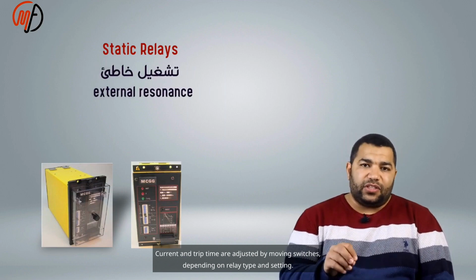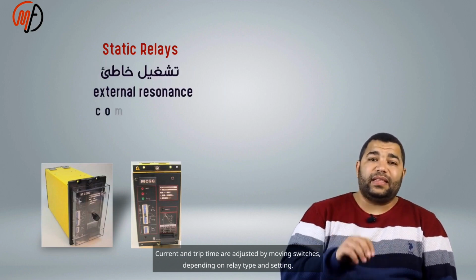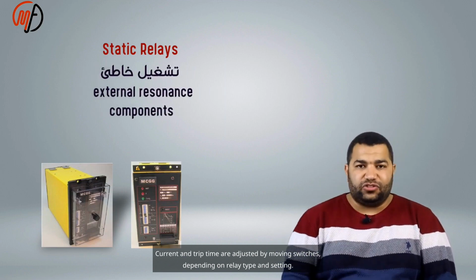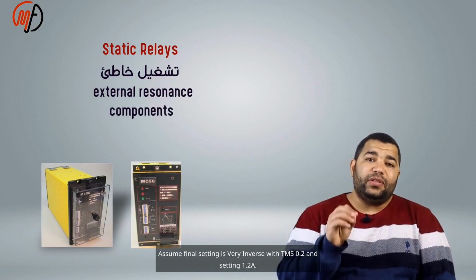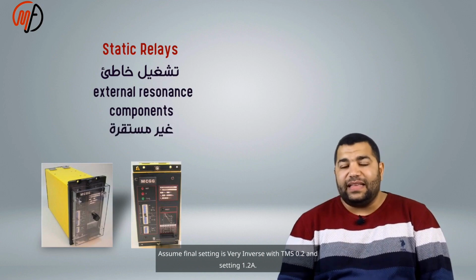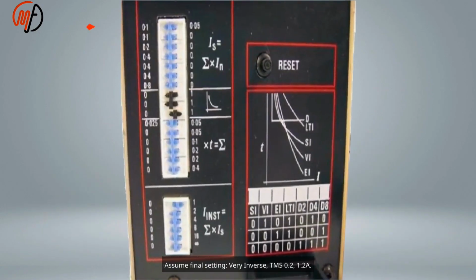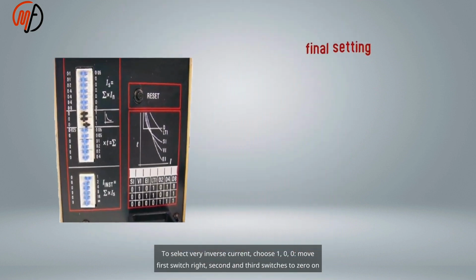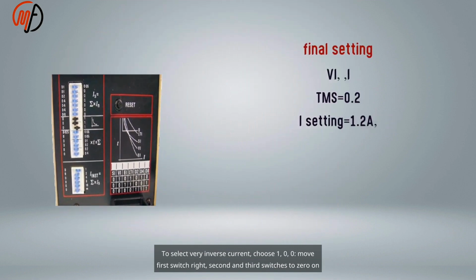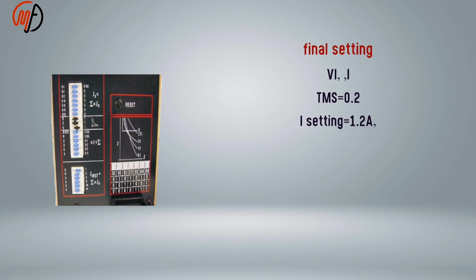Current and trip time are adjusted by moving switches, depending on relay type and setting. Assume the final setting is very inverse with TMS 0.2 and setting 1.2 A. The upper area is for inverse protection, the lower area for instantaneous overcurrent. To select very inverse, choose 1, 0, 0: move the first switch right, and the second and third switches to 0 on the left.